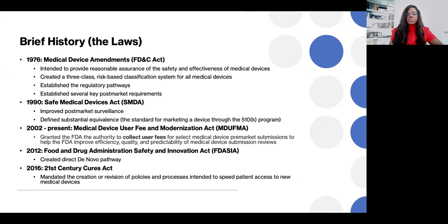And also there's some definition about substantial equivalence. So when we talk about the 510K program, oftentimes there is a description about substantial equivalence because your test has to be substantially equivalent to a legally marketed device. And this was written in the 1990 Safe Medical Devices Act.